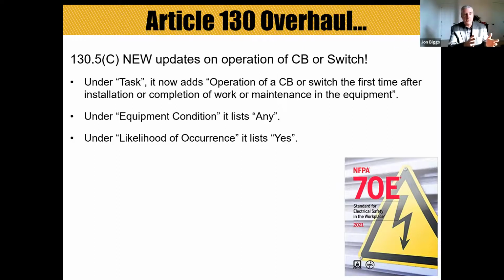So under task, that column, it now adds operation of a circuit breaker or switch the first time after installation or completion of work or maintenance in the equipment. So now they put a time frame on operating a circuit breaker or switch. So the first time after work is done, or the first time after it's newly installed, you have to consider the likelihood of occurrence of an arc flash as yes, it's likely to occur. So that's a big change because in the past, that was not the case. They didn't have a time frame on this. Now they're saying when you operate a circuit breaker or switch, for the first time after it's installed or the first time after maintenance work has been completed on the equipment, you have to consider there's the likelihood of an arc flash occurring.